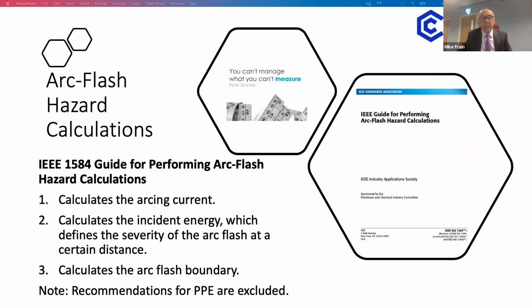Firstly, the IEEE guide will tell you how to calculate the arcing current. It's very important if you wish to design out the hazard on electrical equipment. From that, secondly, it'll calculate the incident energy, which defines the severity of the arc flash at a certain distance in joules per square centimetre, which happens to be the true SI unit, although it's popularly expressed in calories per square centimetre as well. So 1.2 calories per square centimetre, or 5 joules per square centimetre, applied to the skin for 1 second is a threshold at which there could be an onset of a second-degree burn.